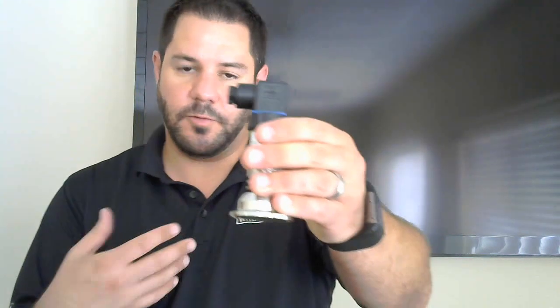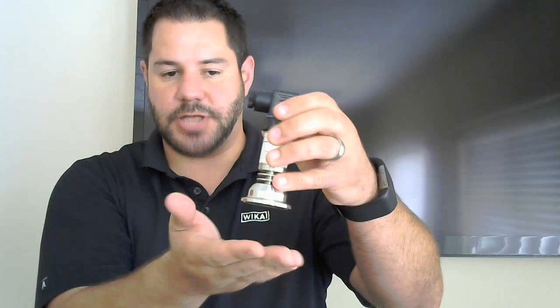So this is just a basic pressure switch. We also can do this in a temperature switch as well. We also have very basic pressure transmitters. If you have somewhere that doesn't need your system logics, like field bus or HART protocol, you could just have a 4 to 20 hookup on this that goes in. This is a great little transmitter to go up against anything in food, beverage, pharmaceutical even, where they don't need to have the logic in the head. They can just have a transmitter that's sending something back to a PLC.